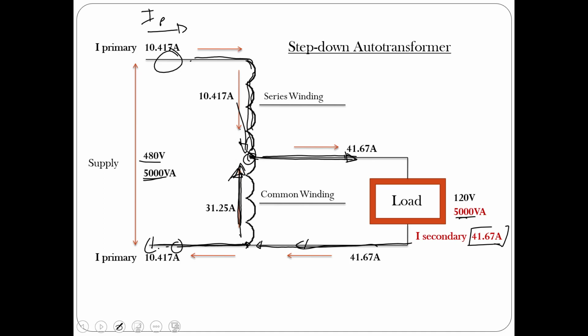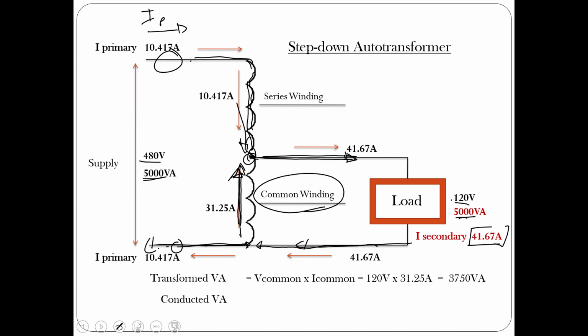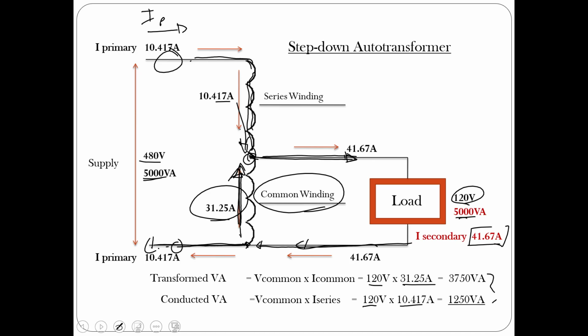Once again, we can do the conducted and transformed VA. Transformed VA, V common times I common. So the common winding voltage is 120. The common current, we calculated it at 31.25. So we multiply 120 times 31.25, we've got 3,750 VA. The conducted VA, V common times I of the series, so the common voltage, once again, 120. The current in the series winding, we figured out to be 10.417. And 120 times 10.417, 1,250 VA. We add up those two VAs, and it should be our original 5,000, and it is.